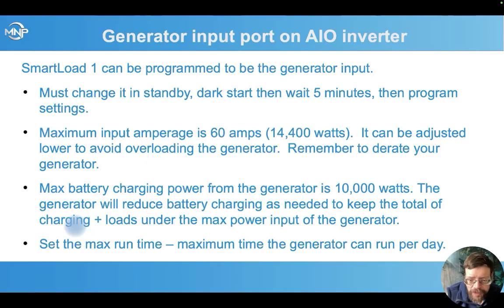You set the maximum runtime, and this is the maximum it can run per day, not per start. If you've got a situation where the generator is starting multiple times per day, usually that's a sign that you've got way too small of a battery bank, unless it's a special situation that only occurs rarely. But if regularly you're running multiple times per day, you really should have a larger battery bank.